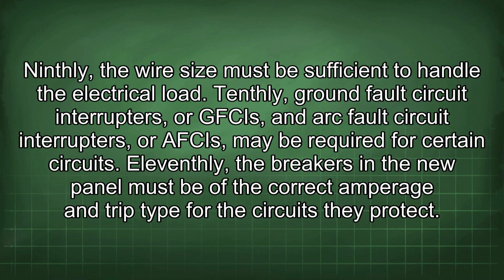Ninthly, the wire size must be sufficient to handle the electrical load. Tenthly, ground fault circuit interrupters, or GFCIs, and arc fault circuit interrupters, or AFCIs, may be required for certain circuits. 11thly, the breakers in the new panel must be of the correct amperage and trip type for the circuits they protect.